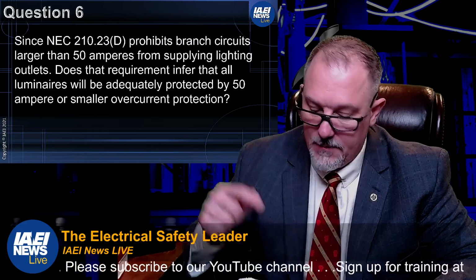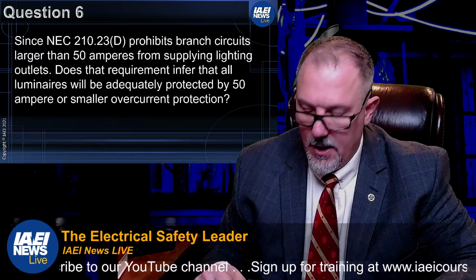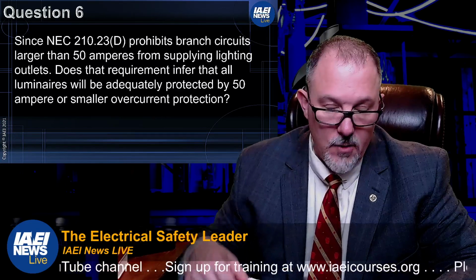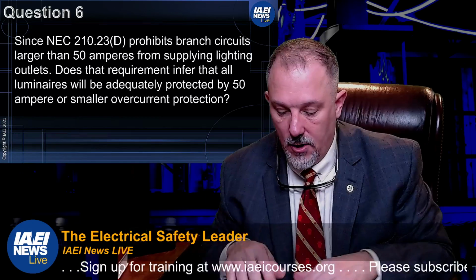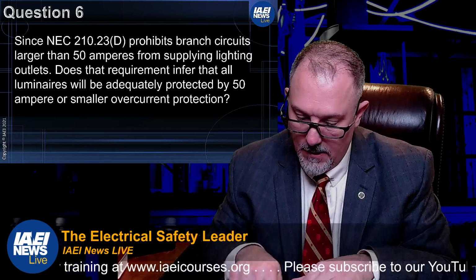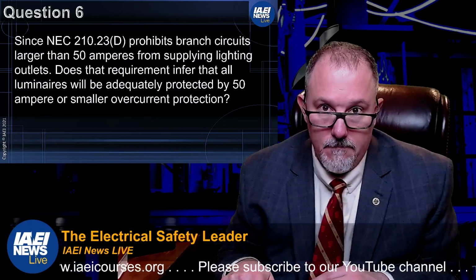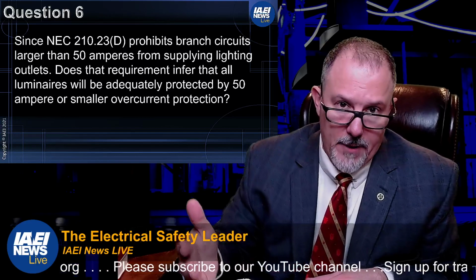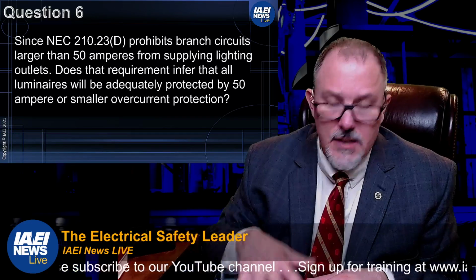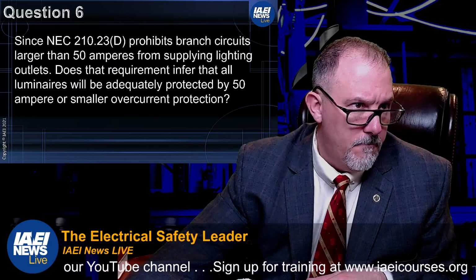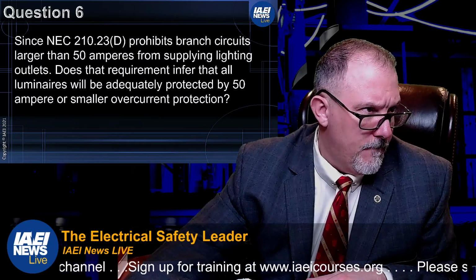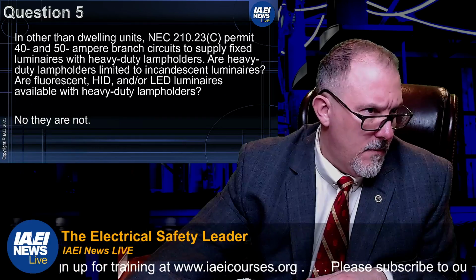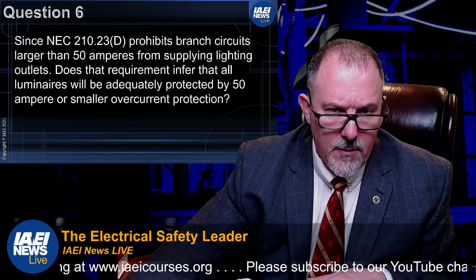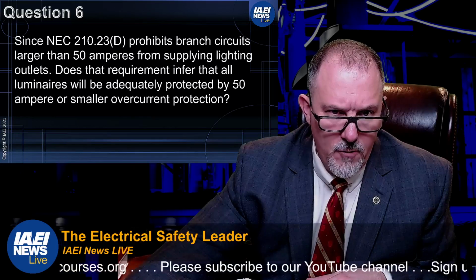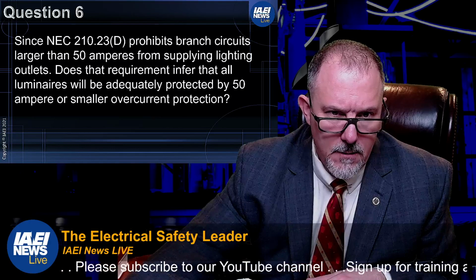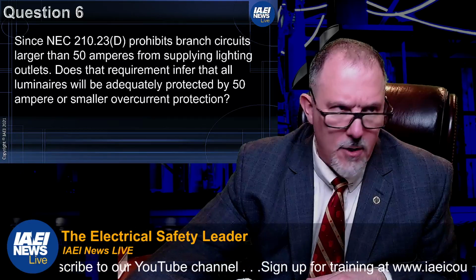It tells us that these branch circuits larger than 50 amps are for non-lighting outlets. So you can't put a lighting outlet on a branch circuit larger than 50 amps. I mean, it's going to be a piece of equipment. It's going to be a load. It's going to be a motor. And remember, this is branch circuits. Okay, so what was the question again? NEC 210.23 prohibits branch. Okay, does that requirement infer that all luminaires will be adequately protected by 50 ampere or smaller overcurrent protective devices?